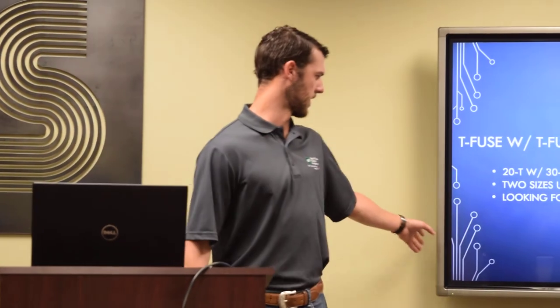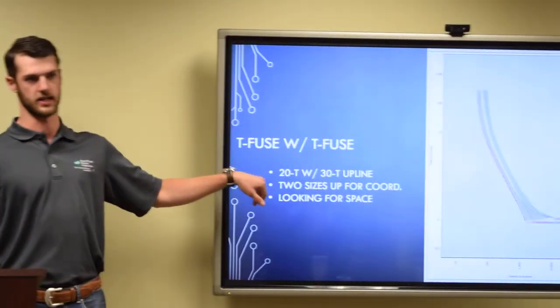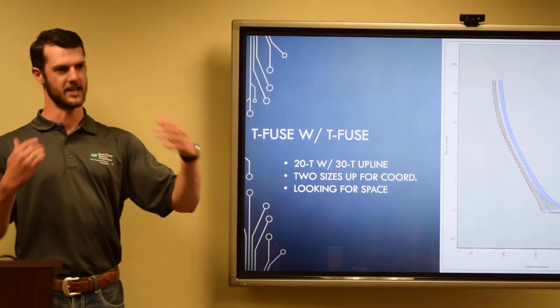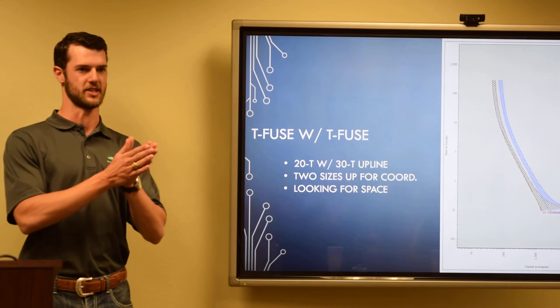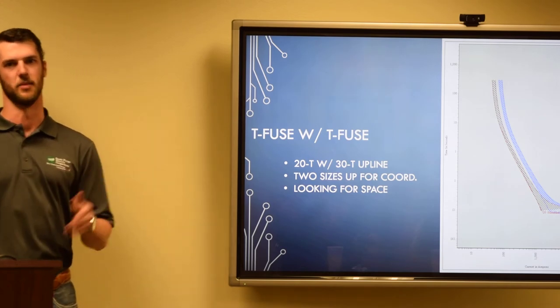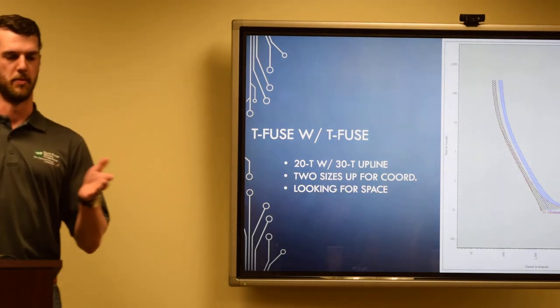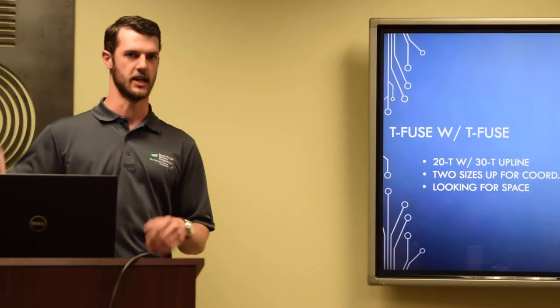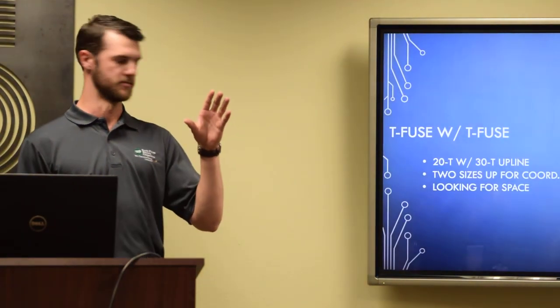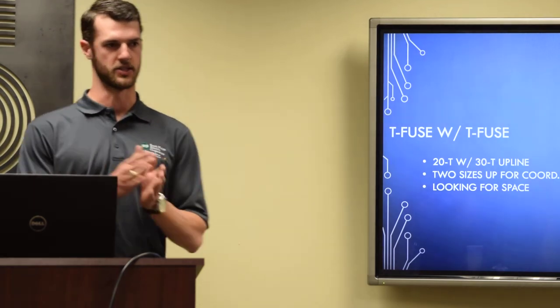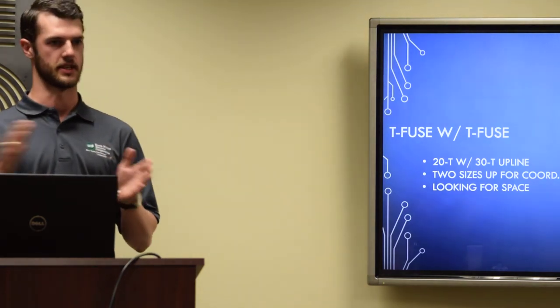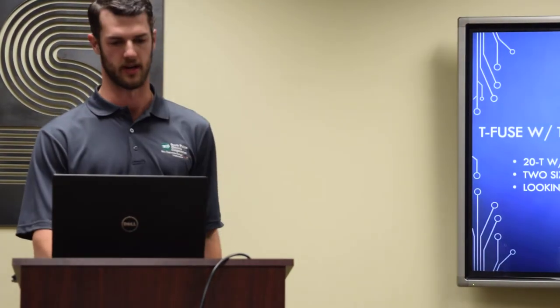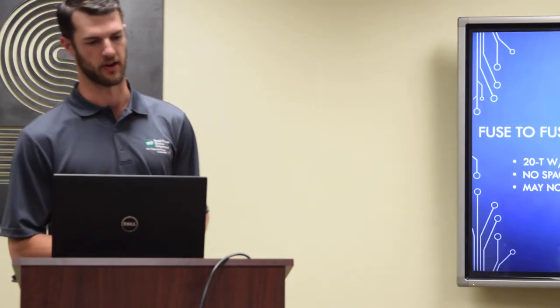When you're out in the field too, this is a good way to double check us that we're not just making up crap. When you're sizing two T fuses, you can usually just go two sizes up for the upline fuse. And that should be about where you want to be. That falls apart a little bit on the really big stuff. But your 10s, 20s, everything just go up two sizes in T fuses, and that's what you should need for coordination. That's a good rule.